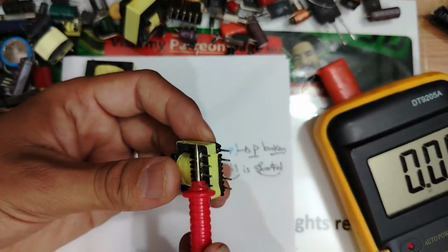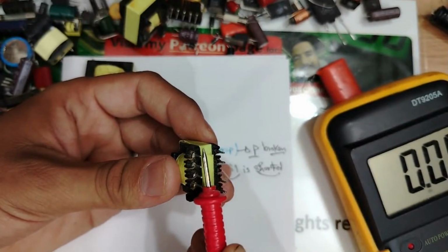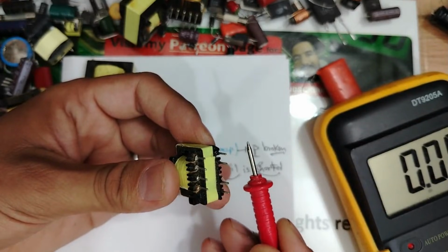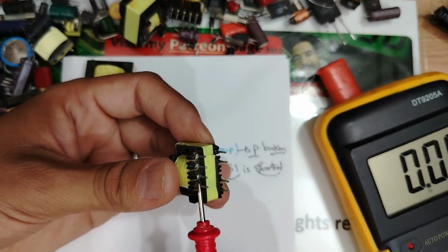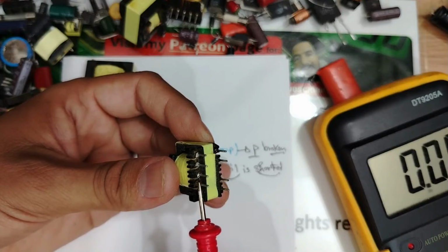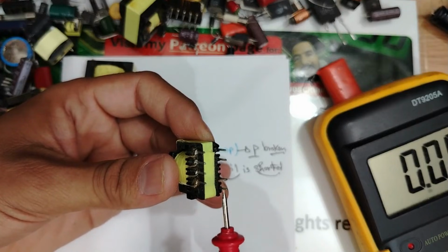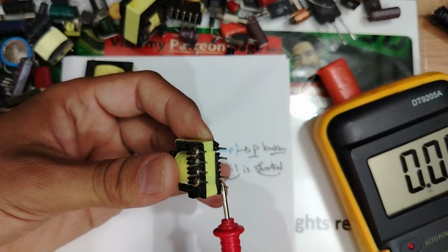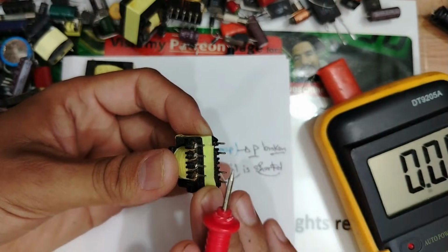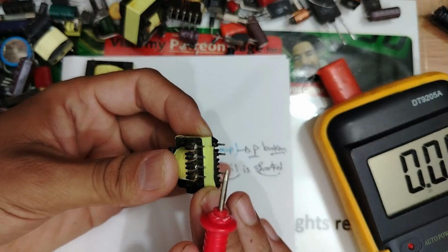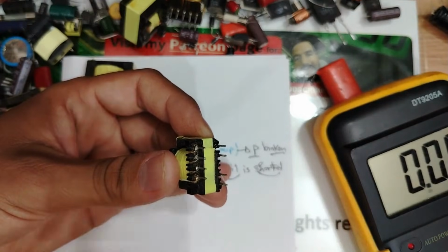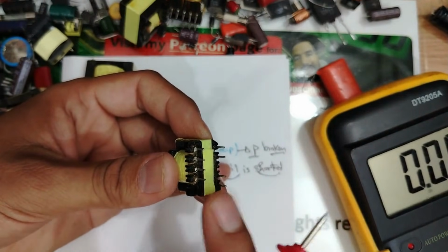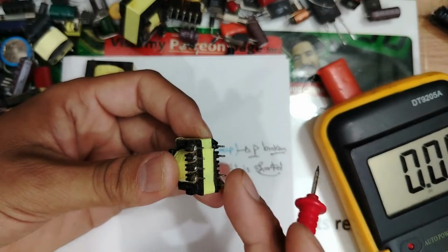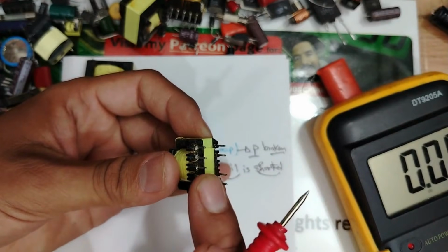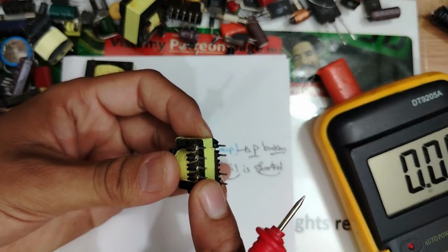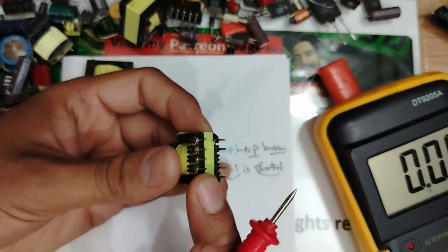Attention please, my friends. Between the primary or input and the secondary or output, if we put one probe on the primary pin and the other on the secondary pin, what should the multimeter show? It should show an open loop, no connection. If there is continuity between primary and secondary, the coils are shorted internally, meaning the transformer is damaged.